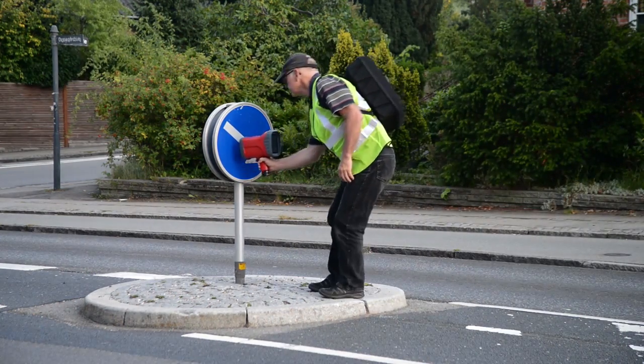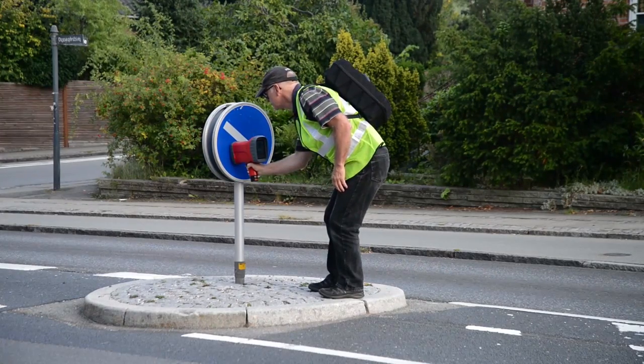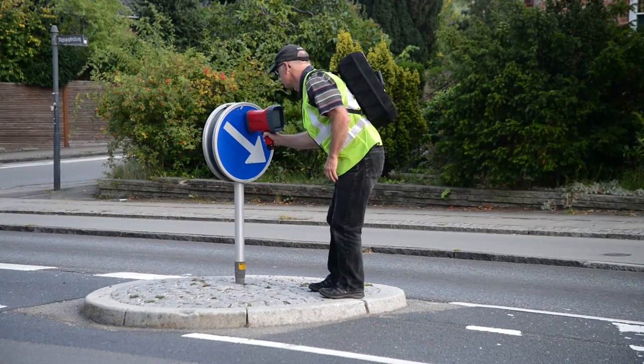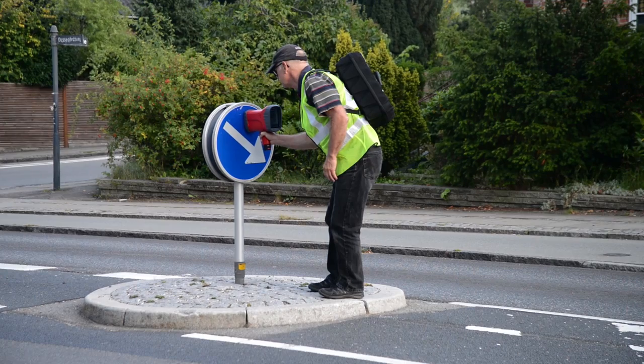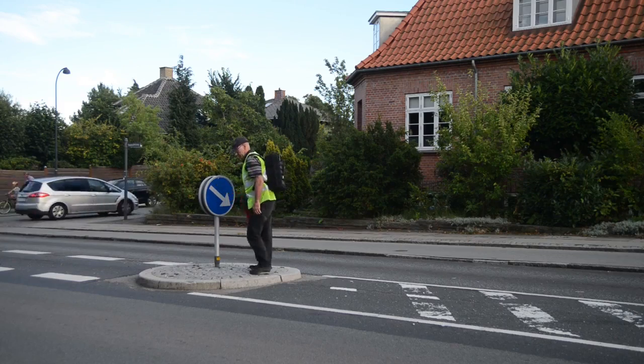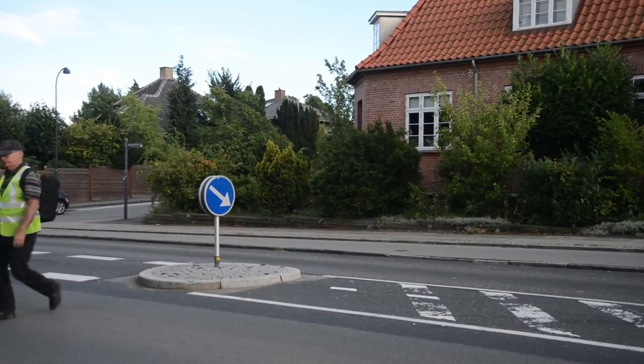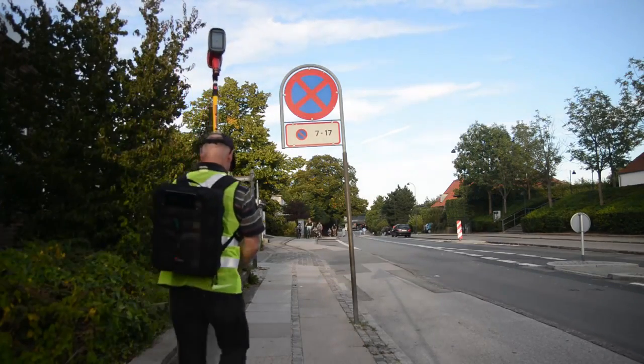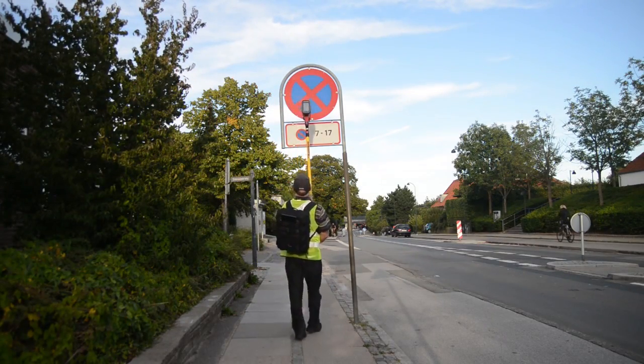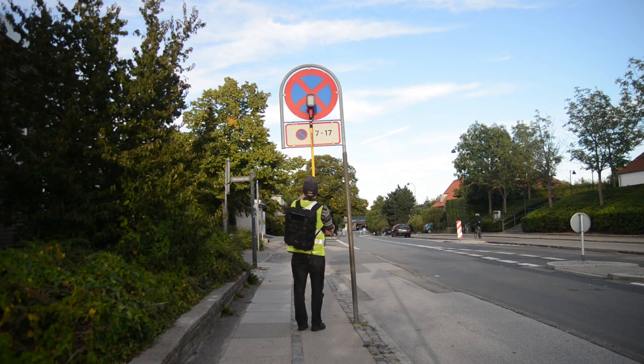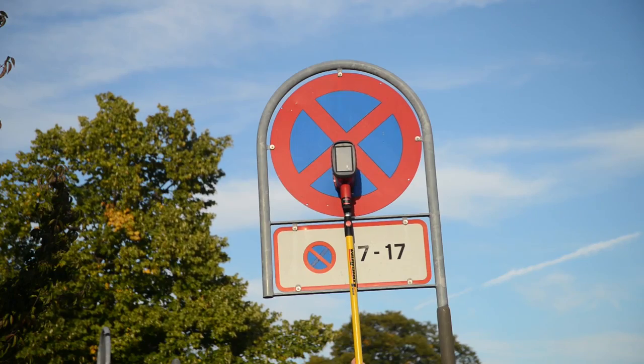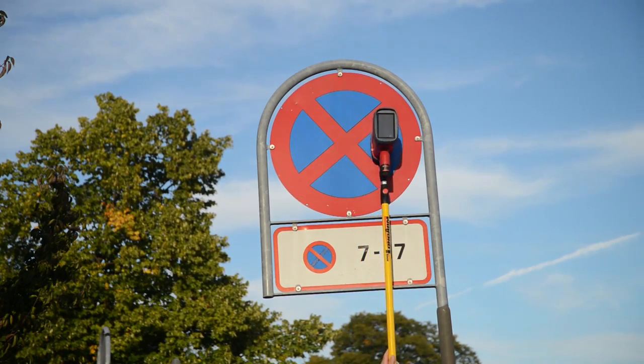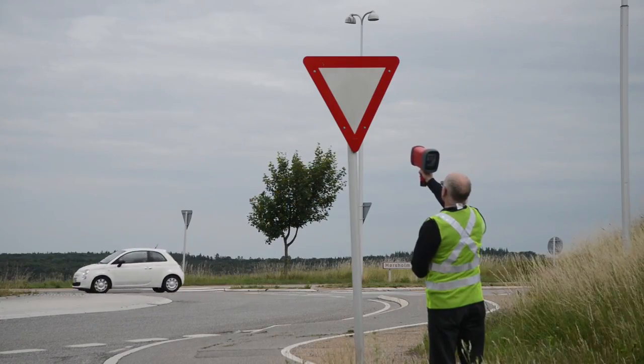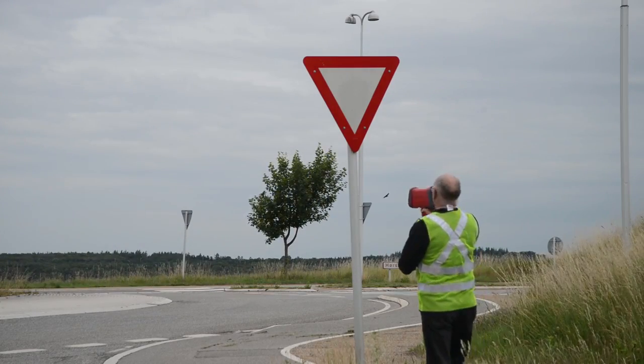Maintenance. The RetroSign GRX is constructed for outdoor use in fair weather conditions. The retroreflectometer can withstand moist weather, but caution must be taken against rain or splashes and dirt from traffic. Even though the GRX is a robust instrument, it is also an optical instrument and must be handled with care. Avoid exposing the instrument to high mechanical shock and vibrations. Avoid exposing the instrument to rapidly changing temperatures.